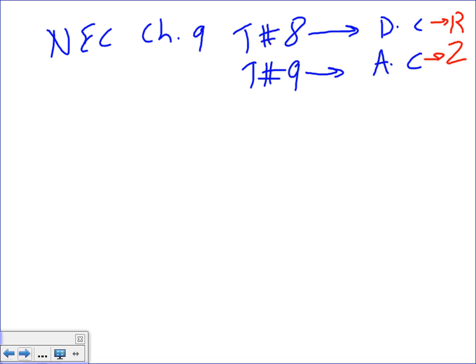Okay? And we'll look at them in a second, guys. For the most part, from statistical analysis, if you look at this book, if your conductors are conductor number 1 all the way to number 4 aught, for the most part, R equals Z.